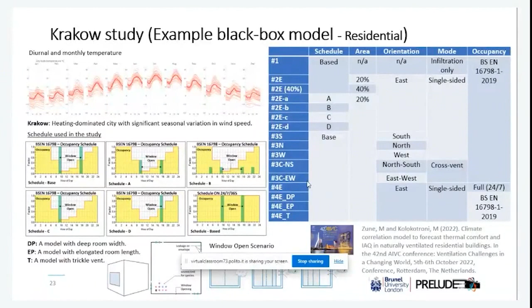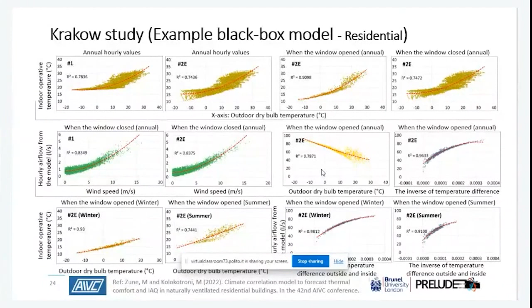This is an example of the temperature and ventilation correlation. We separated the correlation model for window opening hours and window closed hours. The reason is we use wind speed for the correlation during closed hours, and the indoor-outdoor temperature difference for the window opening hours. So we need to develop the correlation equation according to the boundary condition and how the indoor and outdoor parameters correlate with each other.